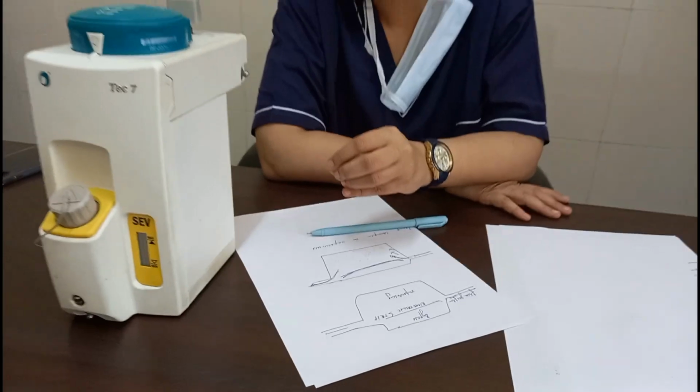If the temperature is decreased in the vaporizer, the bimetallic strip will change its shape and shift towards the bypass chamber, and more and more fresh gas will enter into the vaporizing chamber and be delivered to the patient. Apart from the vaporizer, the bimetallic strip is used in our day-to-day lives in geysers, fridges, heaters, clocks, and most importantly for an anesthetist, in a vaporizer.